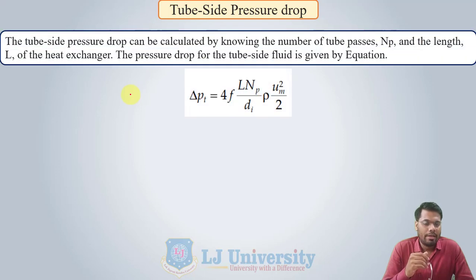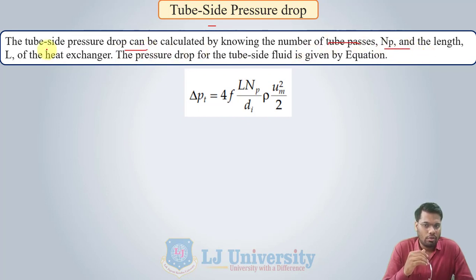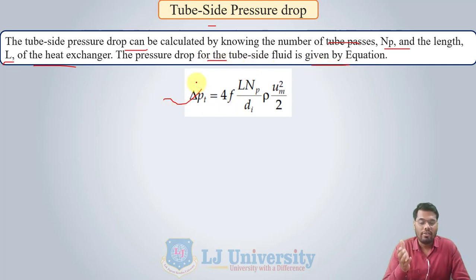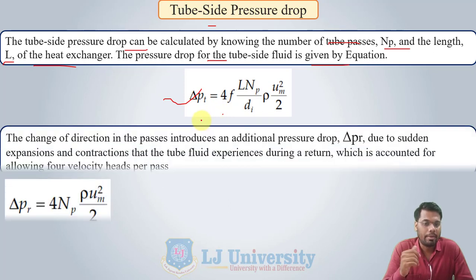Now, for tube side pressure drop — we have already discussed the equation for tube side pressure drop in our previous lecture, so let us revise it. The tube side pressure drop can be calculated by knowing the number of tube passes Np and the length of the tube, which are parameters already decided in our preliminary stages. The pressure drop for the tube side is given by the Fanning equation, which we have already discussed in our compact heat exchanger chapter.